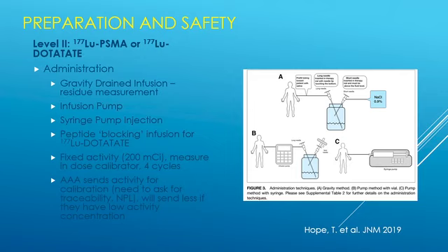AAA is the example of a company that has evolved from diagnostic and is not necessarily as rigorous as you would like them to be. They will send you activity. They won't necessarily tell you that it's traceable, or give any indication on how to do your dose calibration. Of course, that's not that difficult, but you want documentation for traceability, and it's really hard work to get them to send it to you, and their traceability currently is to the National Physical Laboratory in the UK.